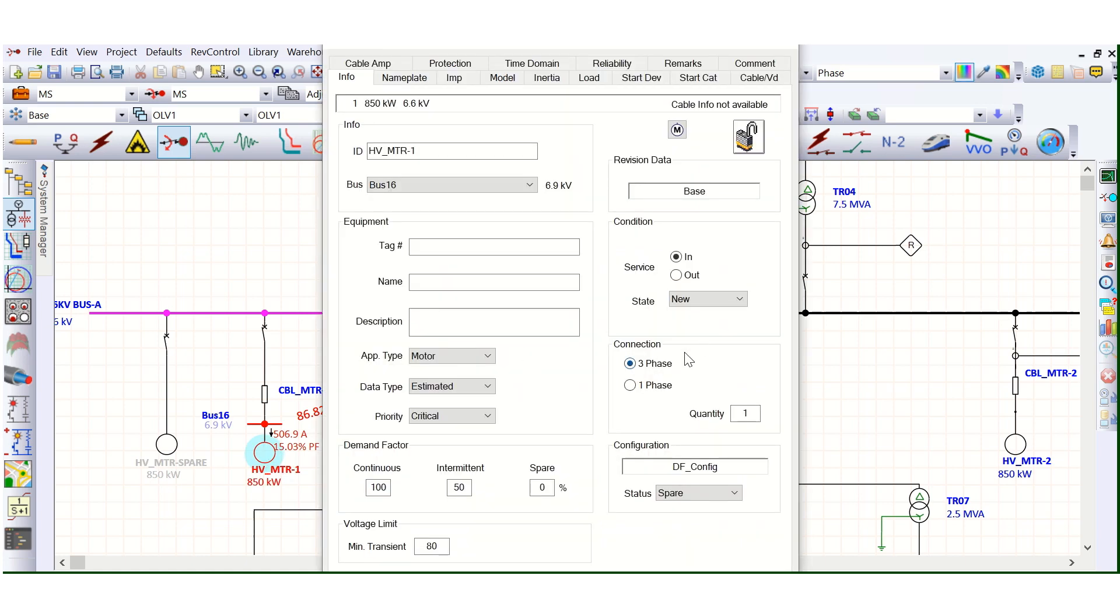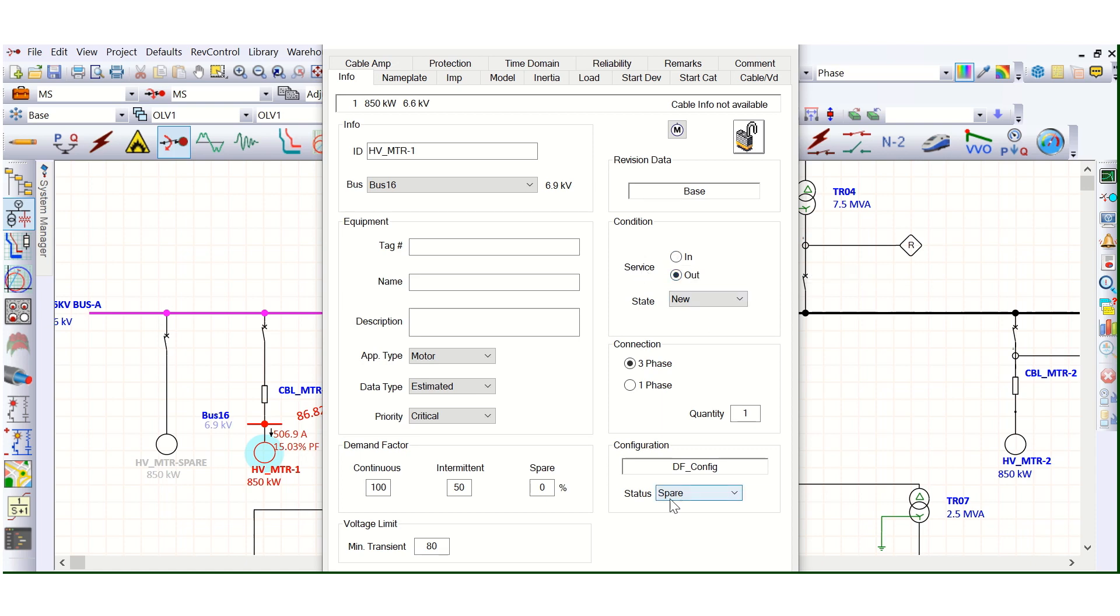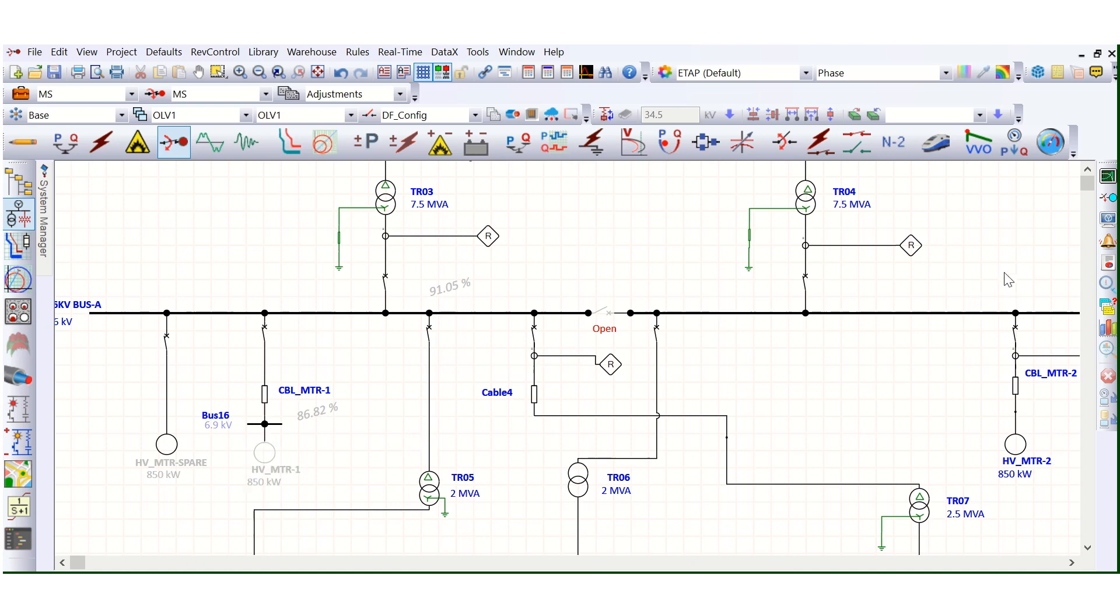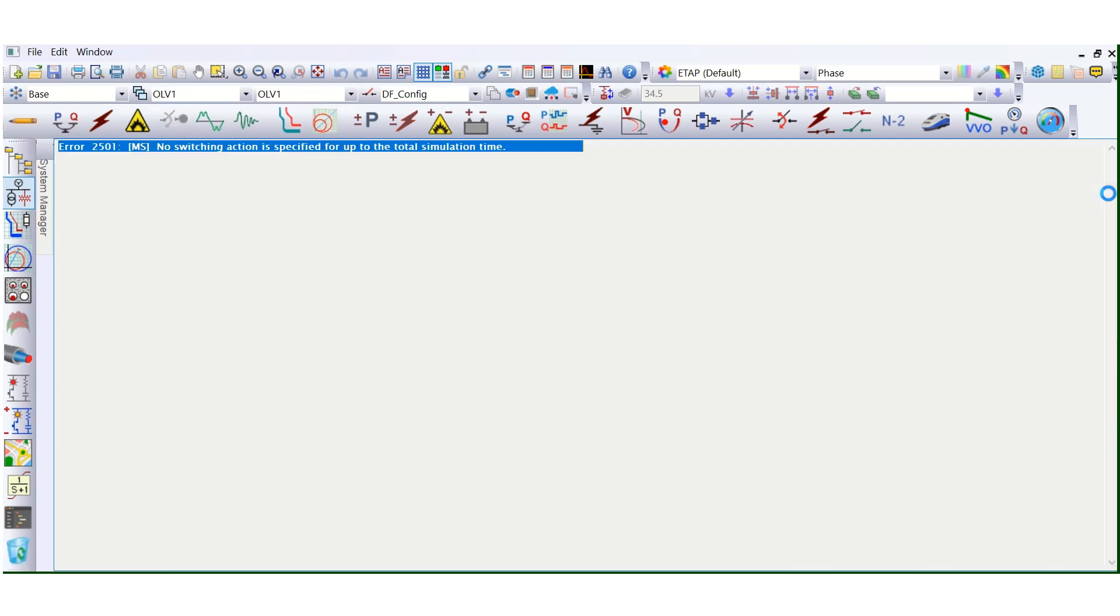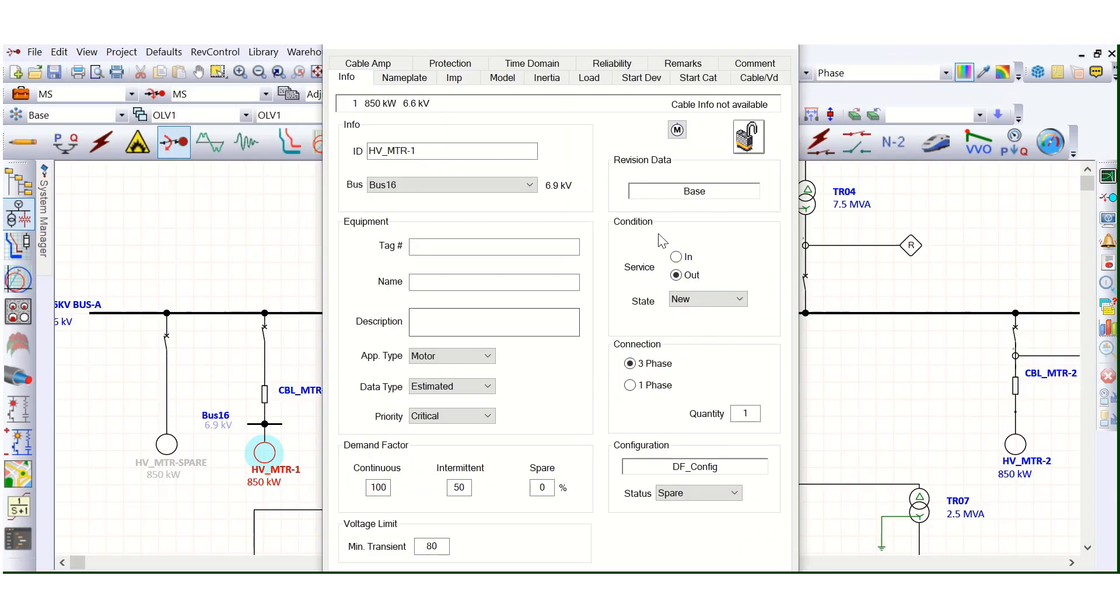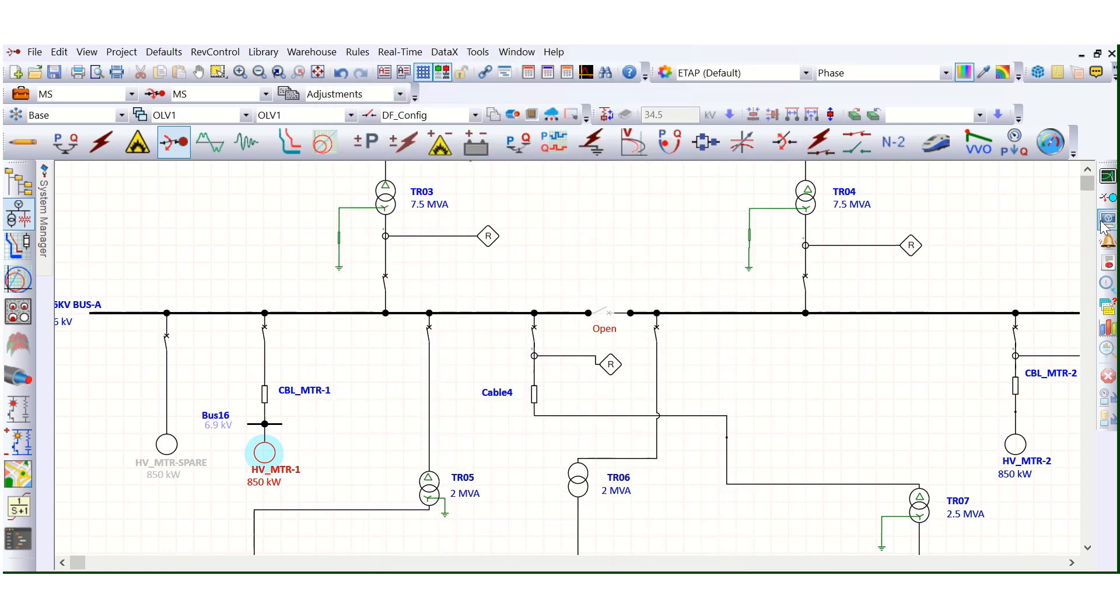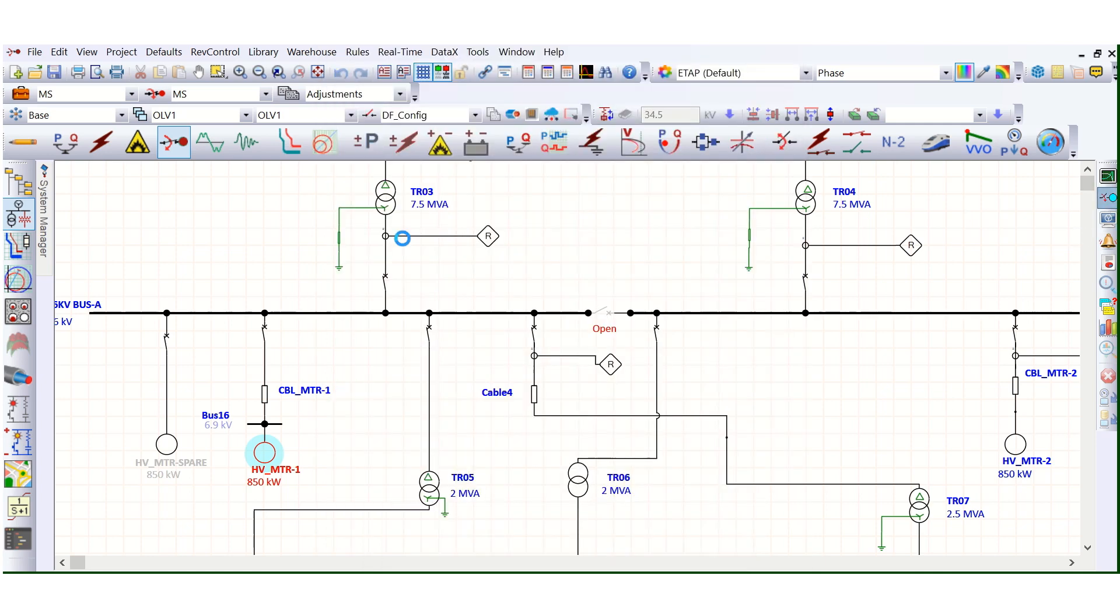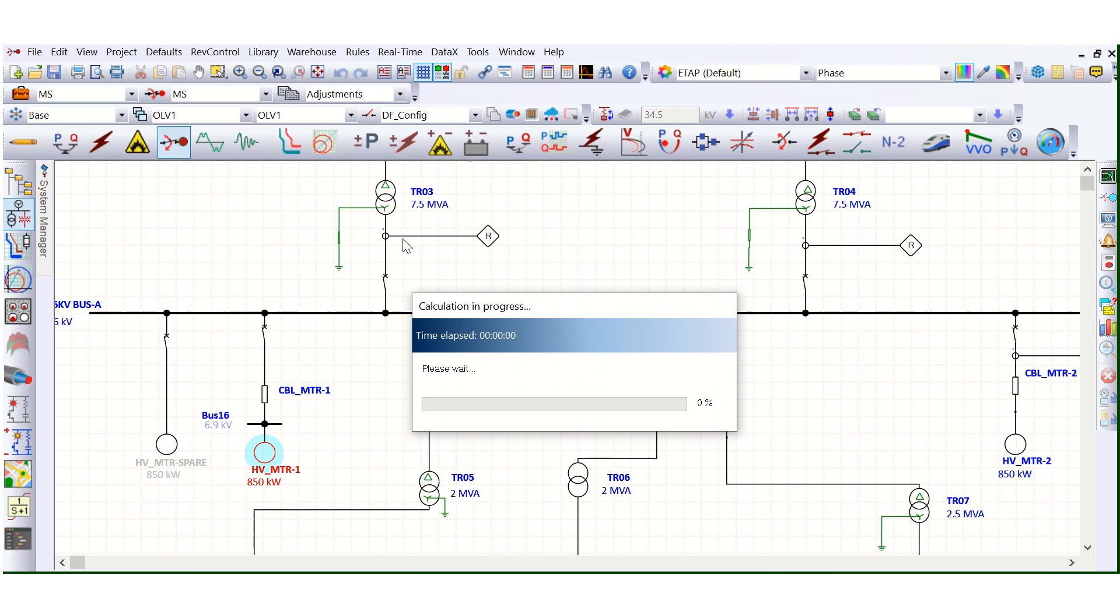So now it's working. If we change this, just to cross check, if we change this service out, but it is in service mode. Now you run. It will show that error. That error 2501. No switching action is specified. So this is because of this motor only. This is because of this service in or service out position.